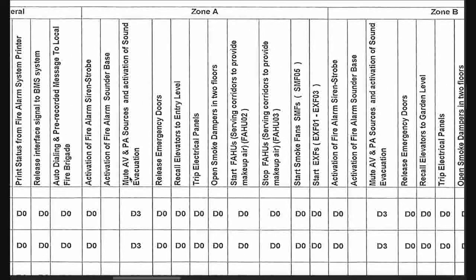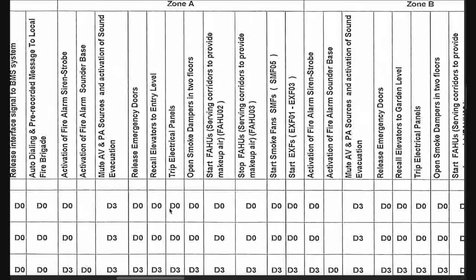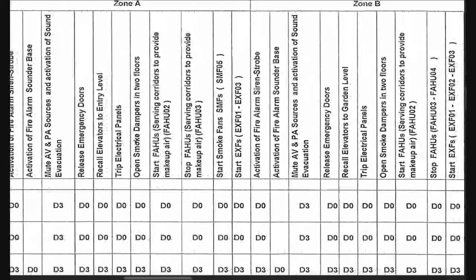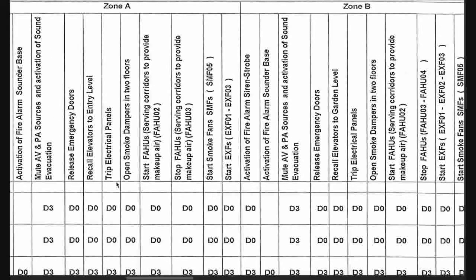Then, mute audio, visual, and public sources and activate the evacuation sound after 90 seconds. Release emergency doors and access controls immediately. Recall elevators to the entry level — the escape floor — immediately. Trip electrical panels immediately.